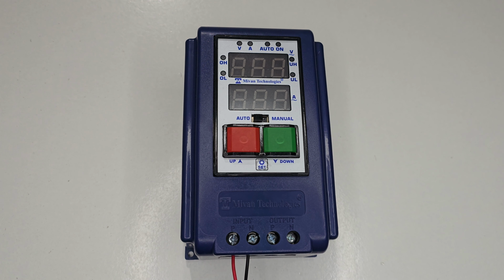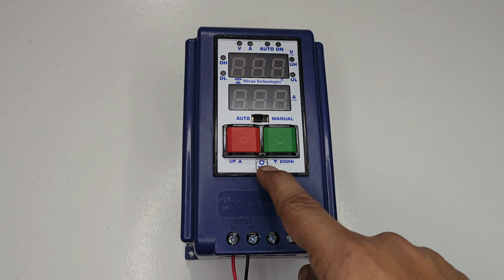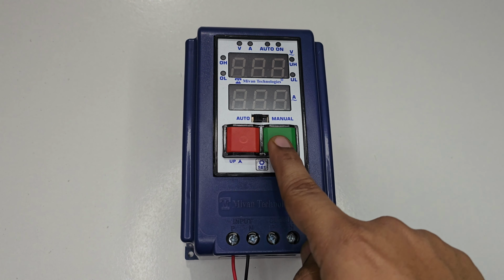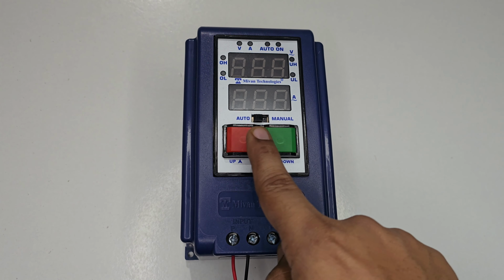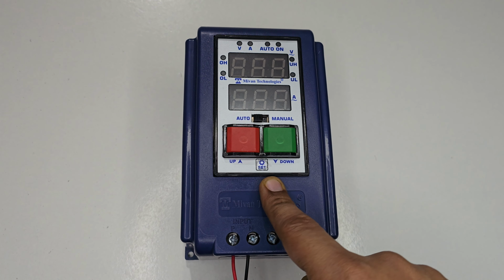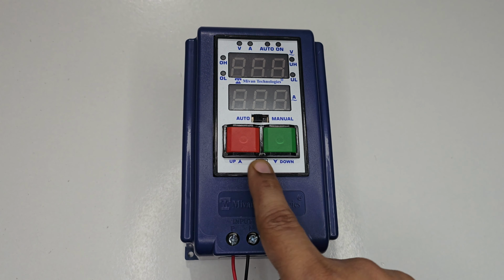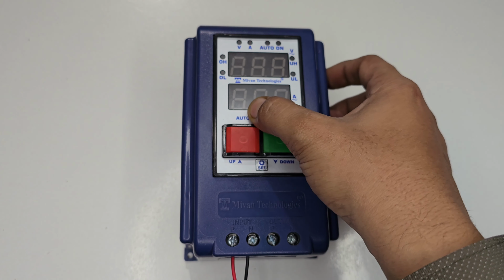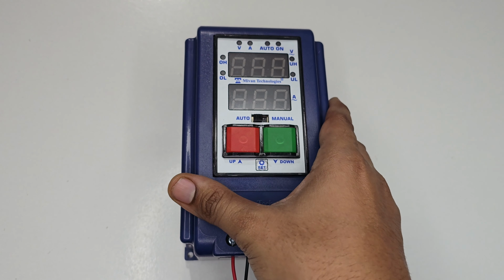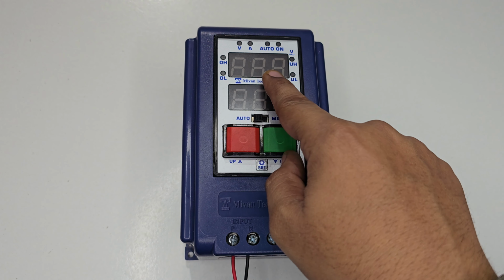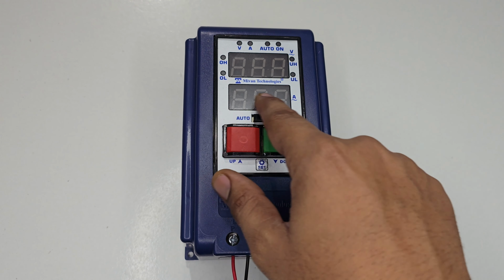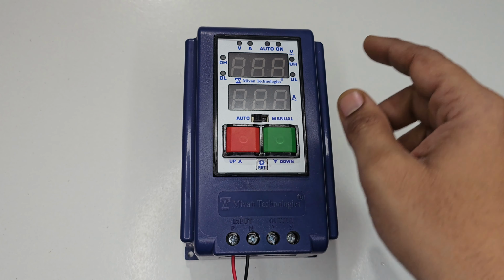Now I'll show you how to connect the device. In this device, these are the input terminals, these are the output terminals, this is the programming key, and these are the start and stop buttons to start and stop the motor in manual mode. These keys are also used as up and down keys in programming mode. This is the auto and manual switch. The upper display shows the voltage, the lower display shows the ampere.